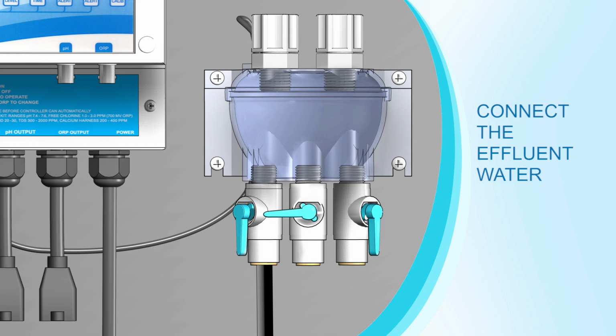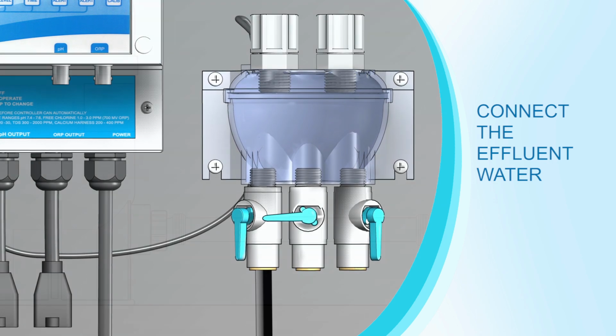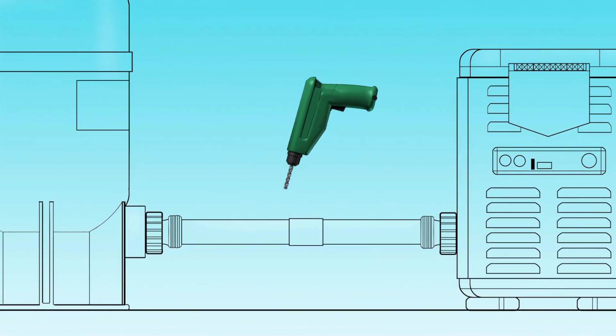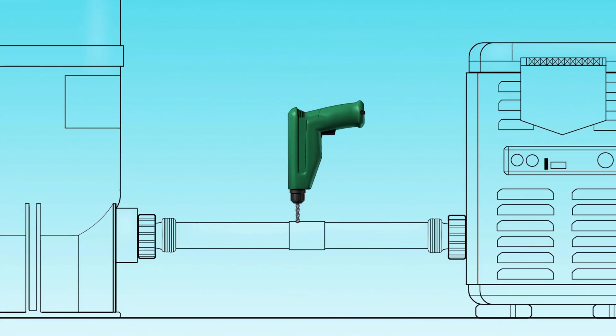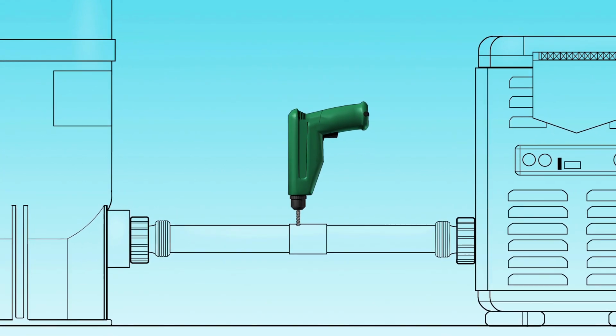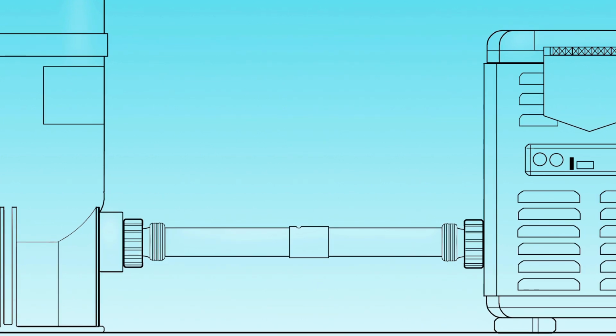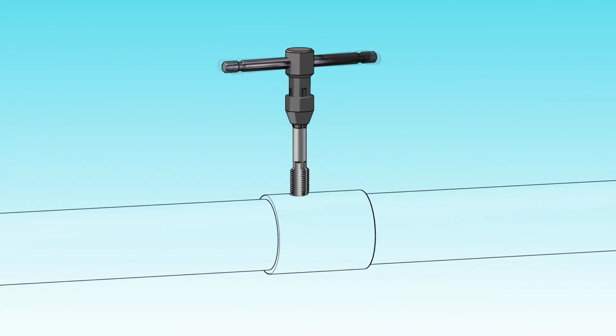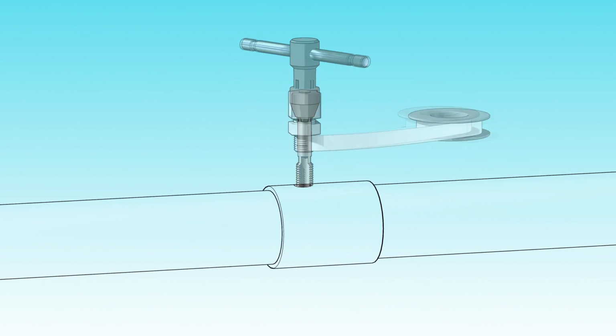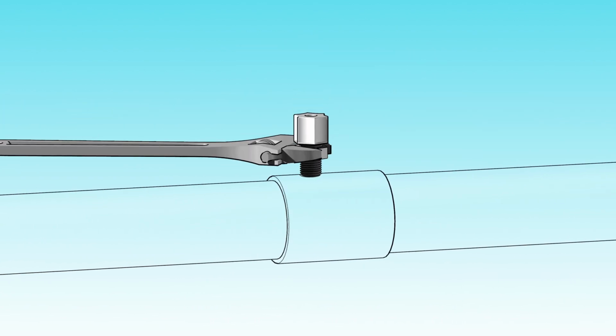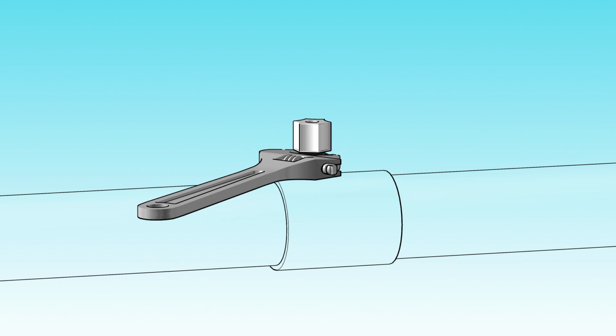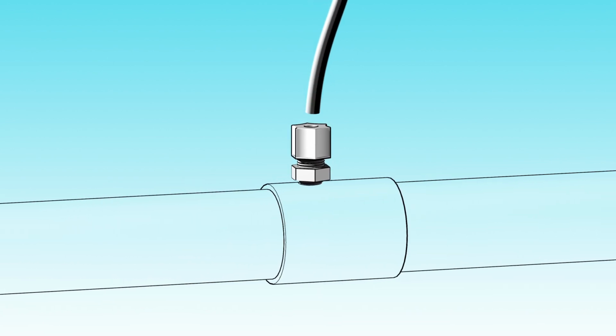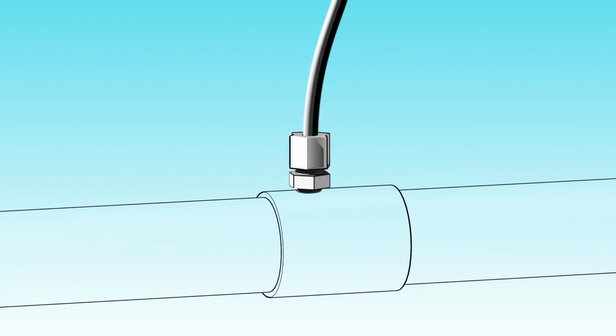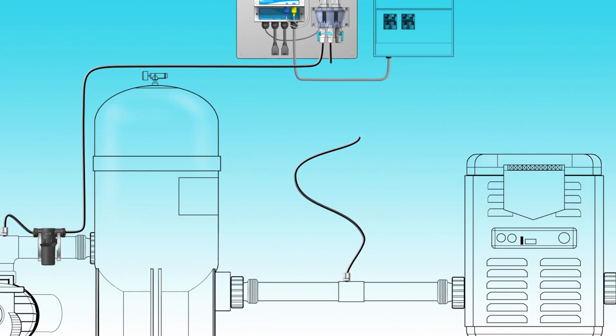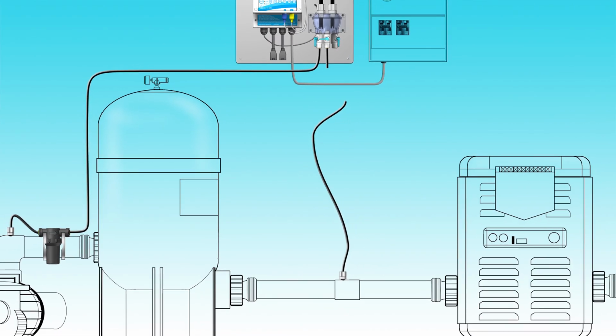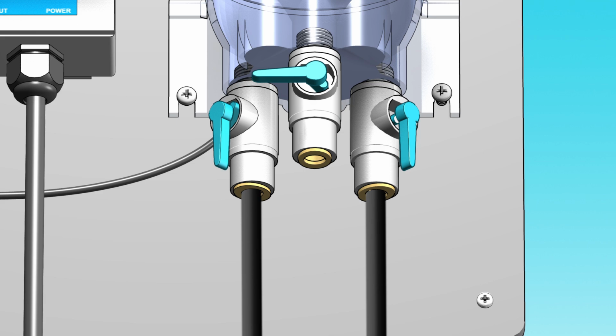Connect the right-hand or effluent valve on the flow cell. Drill a hole in a section of the pipe beyond the pool filter. Tap the hole and screw in the additional compression fitting. Insert one end of the tubing into the fitting and hand tighten. Insert the other end of the tubing into the right valve of the flow cell.